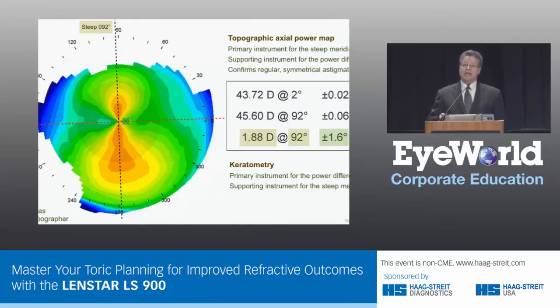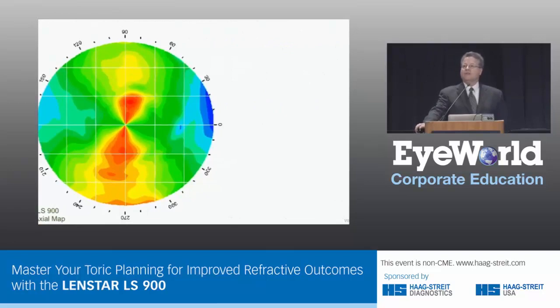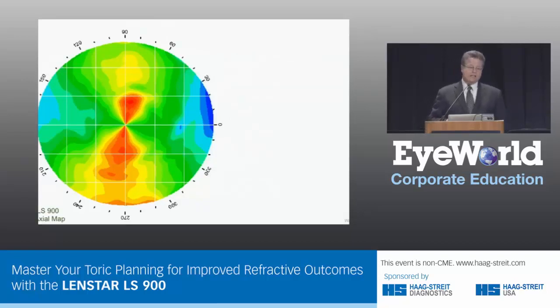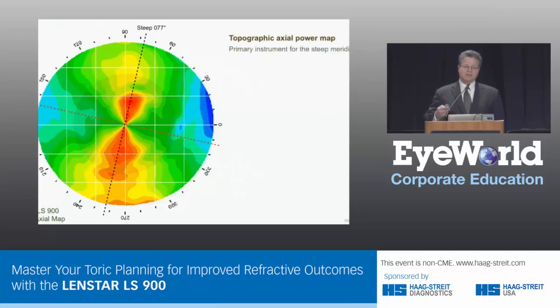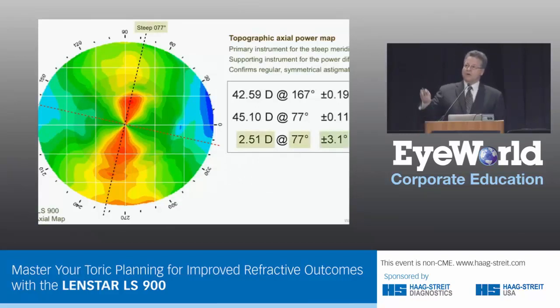So let's look at another axial map. This is the T-cone from the LENSTAR. Believe it or not, the LENSTAR actually has a device that sits on the front that gives us an axial topographic map, looking very much like the Zeiss Atlas 9000 topographer. There's our 3-millimeter zone, our steep meridian, and our flat meridian. To repeat: this is primary for the steep meridian and secondary for the power difference. There are our Ks — we make sure the two line up properly — and now we know the orientation of the steep meridian and the power difference between them.